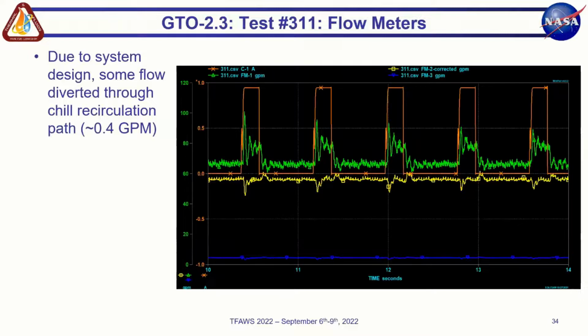The flow meters, now, this is one where we had to divert some amount of flow through the recirculation path for the sake of system stability. The recirculation path would basically be downstream of the pump, and it's a path to bypass the thrusters and send flow back to the tank. This is what we're seeing in flow meter 1, the total flow. I believe flow meter 3 is capturing some of the recirculation flow, and we do see some larger changes in flow rate here as we go to more thrusters under longer pulses.